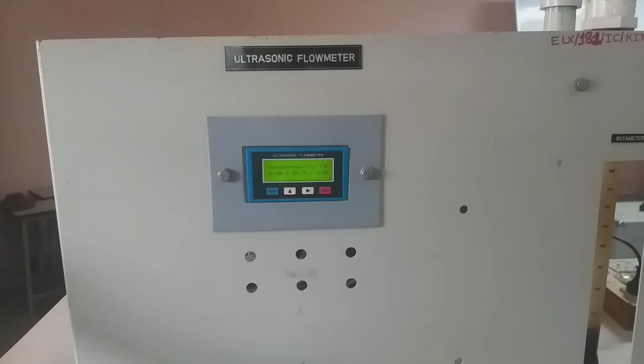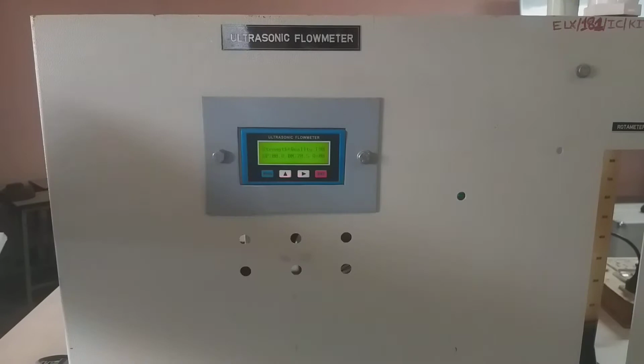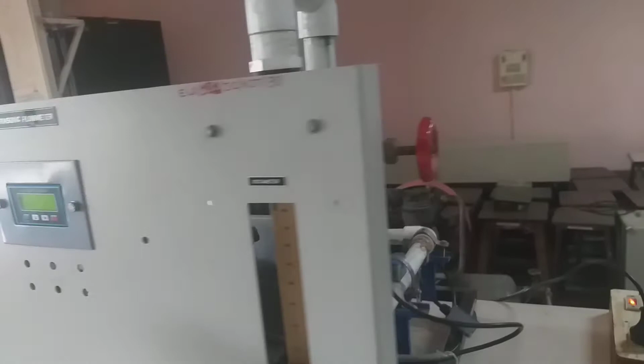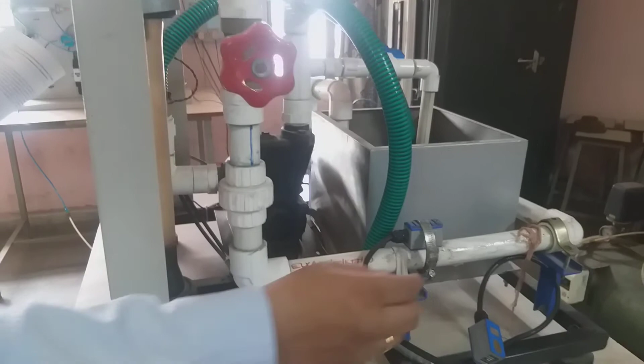This UFM 2000M is a transit time flow meter which utilizes two transducers, functioning as both ultrasonic transmitter and receiver. Transmitters are clamped on the outside of a closed pipe, as shown here. This ultrasonic transmitter is indicated, and at a specific distance we have kept the receiver, so we can detect the waves transmitted by the transmitter. The transducer can be mounted using the V method.